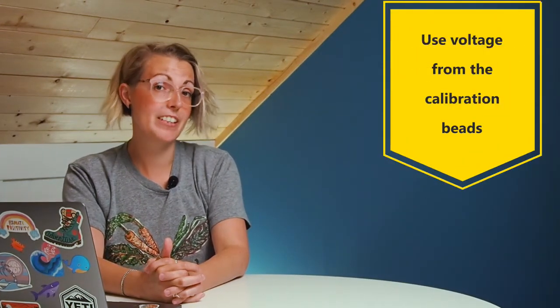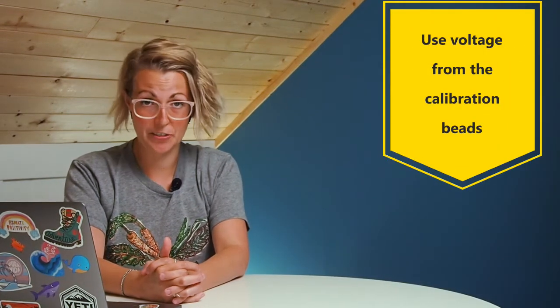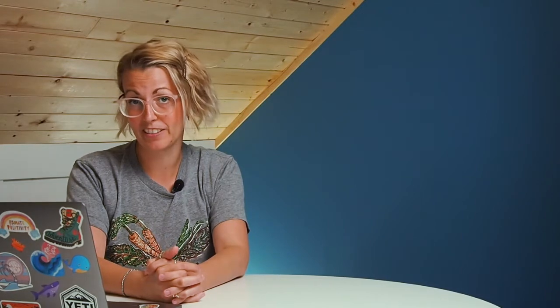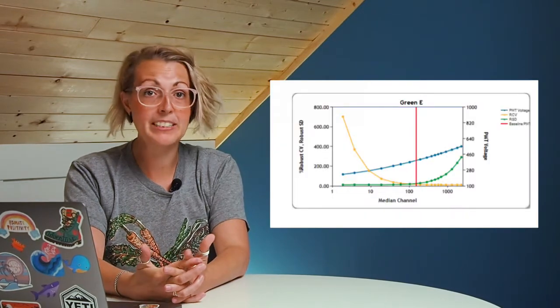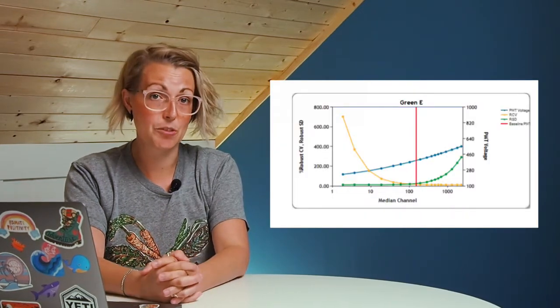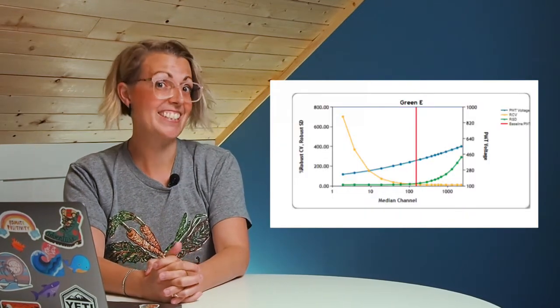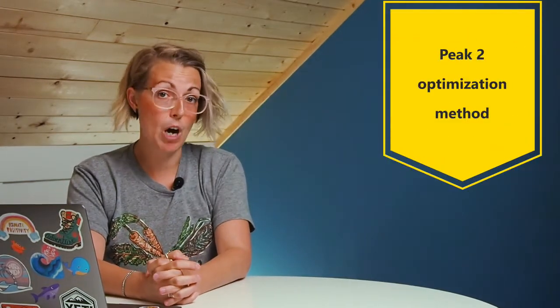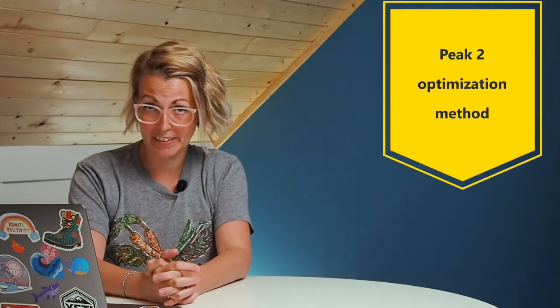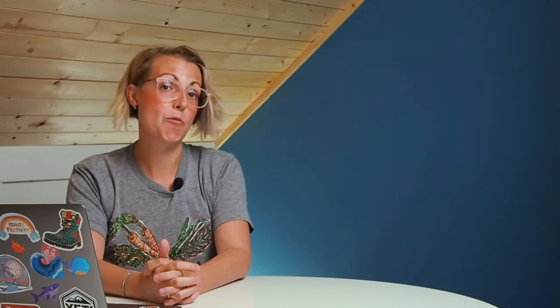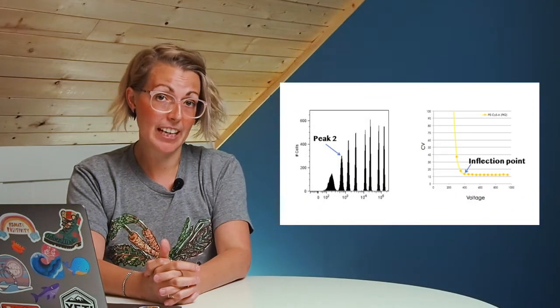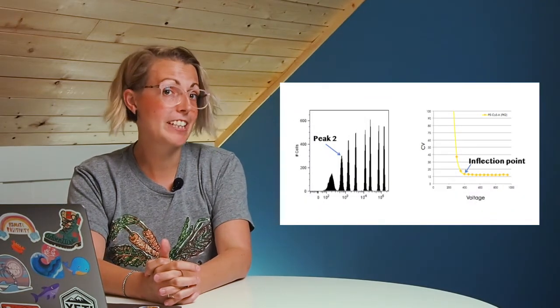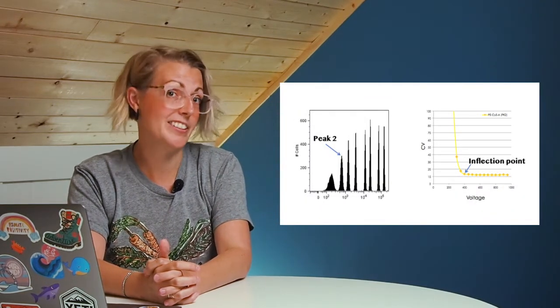When it comes to optimizing your voltages, there are a few different methods you can use. Some are very labor intensive, some require basically no work at all. The easiest method is just using the voltage values given from the calibration beads. On the BD machines, this would be your CS and T values. A more labor intensive method is using the peak 2 optimization method, where you use 8 peak rainbow beads and look for the inflection points in the detection.